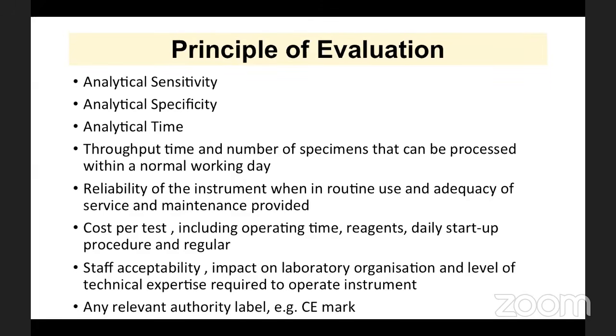And how much time a machine will take in analyzing a single specimen. Then you check throughput time. Suppose you have to provide 3-4 wash cycles after analyzing 20 specimens, or you have to shut your machine for half an hour or 1 hour after analyzing 40 or 30 samples. This will decrease your throughput. Your analytical time may be less. And the reliability of your instrument in routine use, and adequacy of service and maintenance provided. Suppose there is frequent breakdown, you have to call your company engineer again and again for various things, then reliability will be doubtful. Cost per test. Sometimes we think, okay, in this machine, our reagent cost is 15 rupees per test.